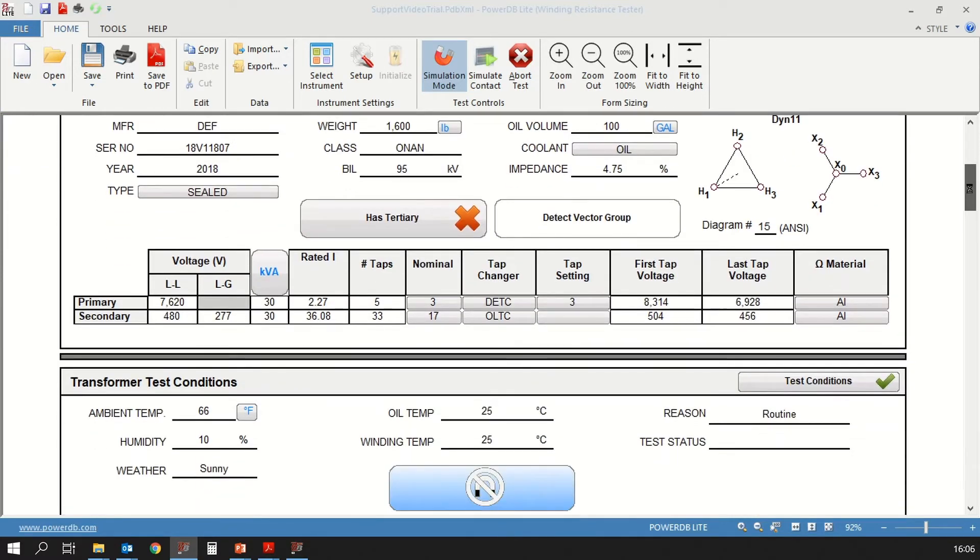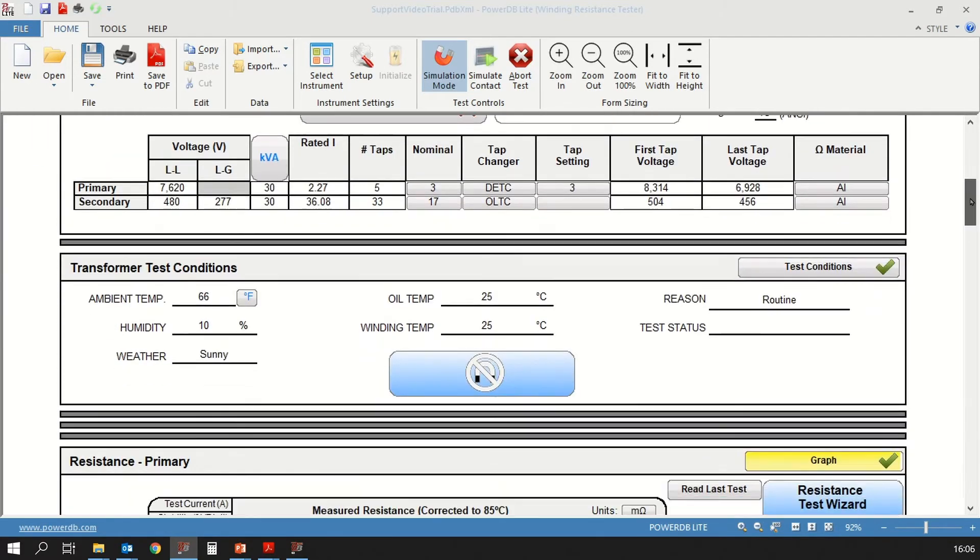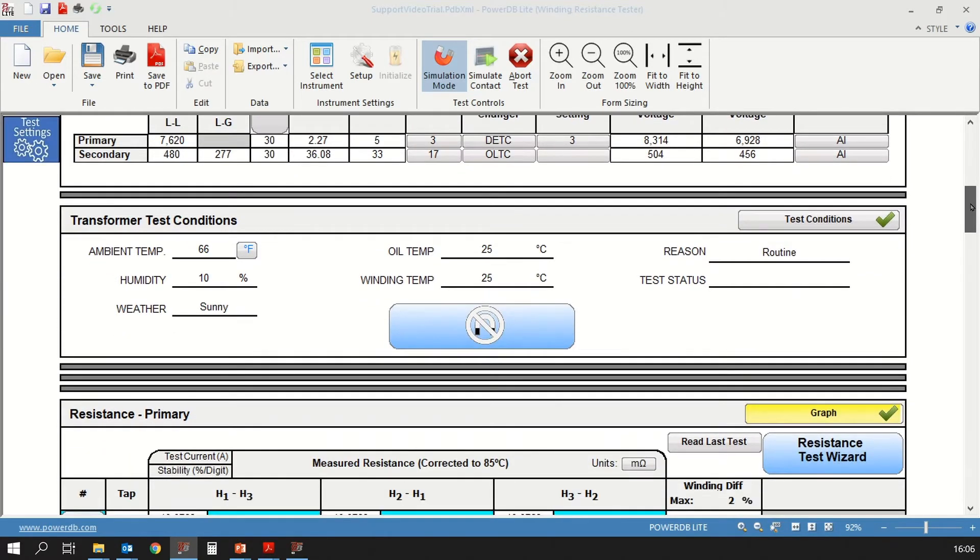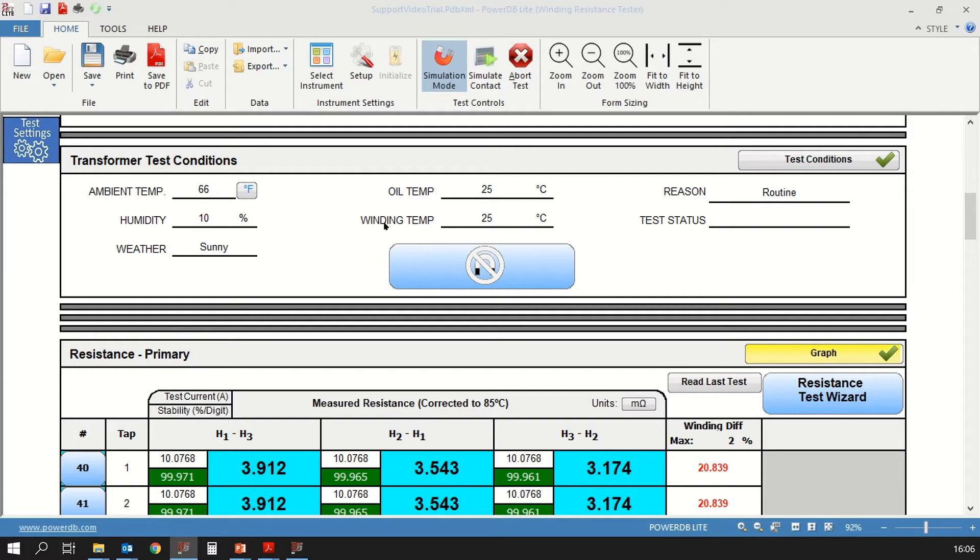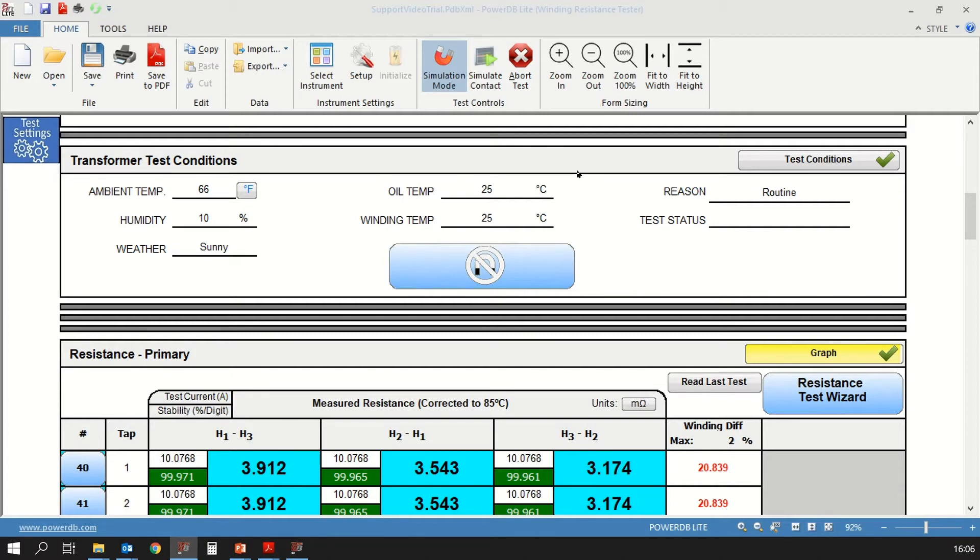Now we move on to the transformer test conditions section. Here you have information that needs to be input in regards to ambient temperature, humidity, weather, oil temperature, winding temperature, the reason you are testing and the status of the test. Winding resistance measurement is dependent on temperature, so it's important that this information is recorded.